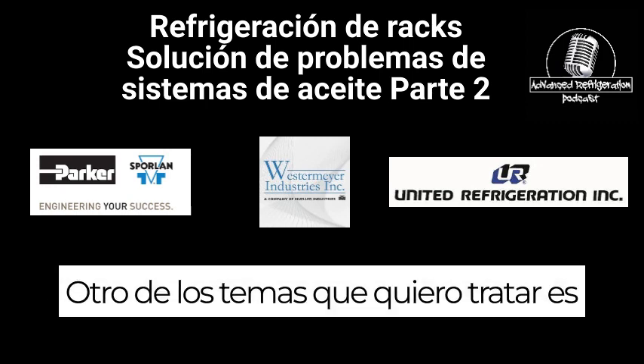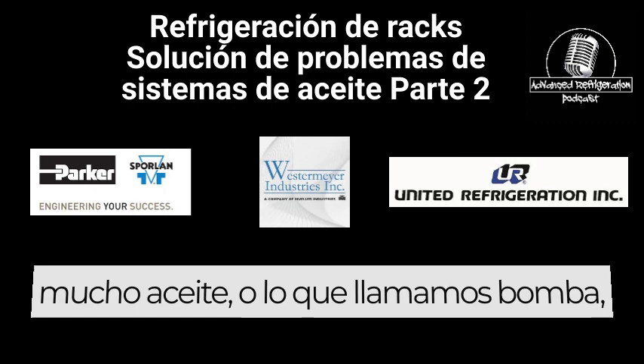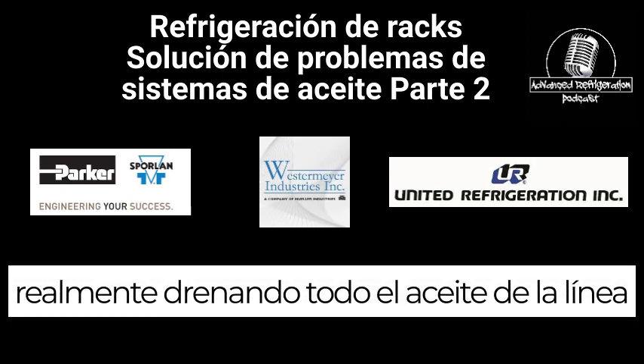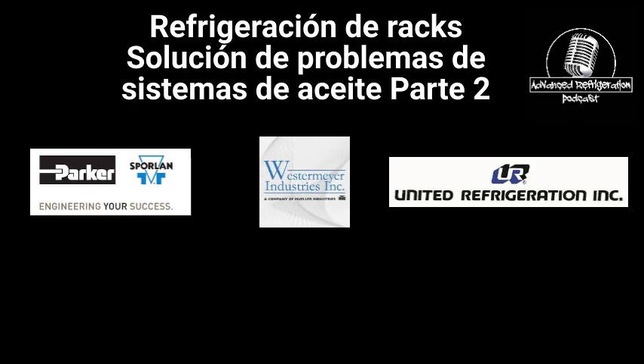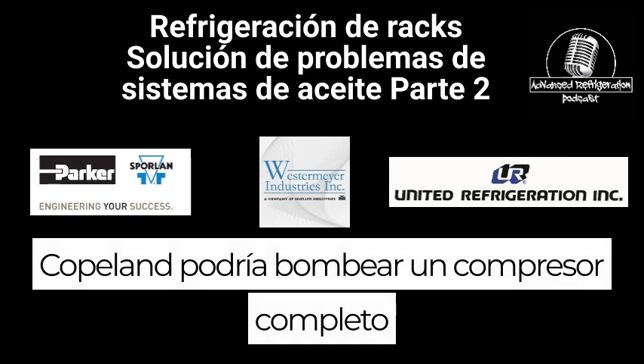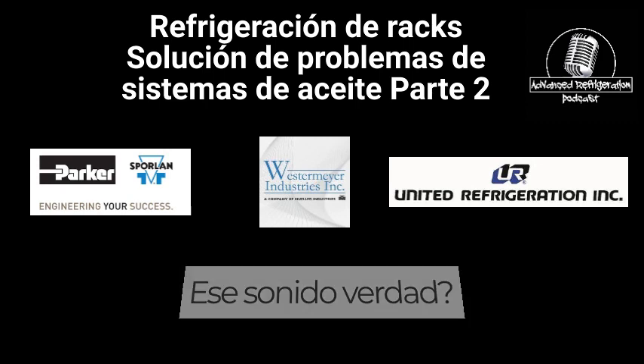One of the other issues I want to cover is when you have a compressor that's sucking out so much oil, what we refer to as a pumper, one that's sucking out so much oil that it's draining all the oil out of the line as well as the oil reservoir. Typically, a 4D Copeland might pump out a whole compressor in, I don't know, probably an hour and a half, right? Does that sound right?